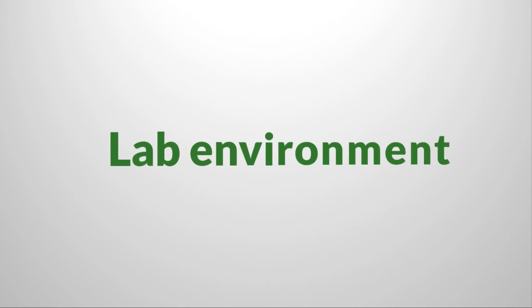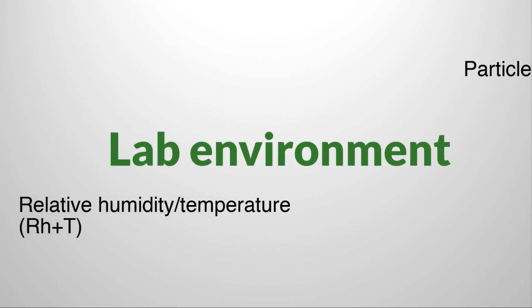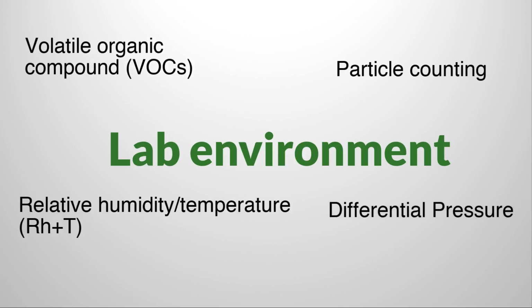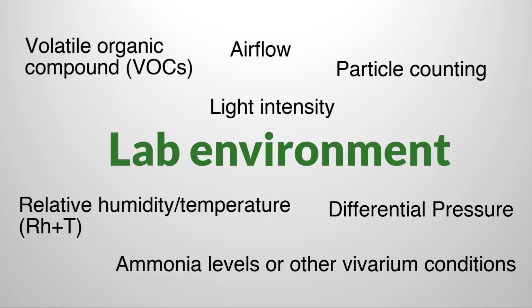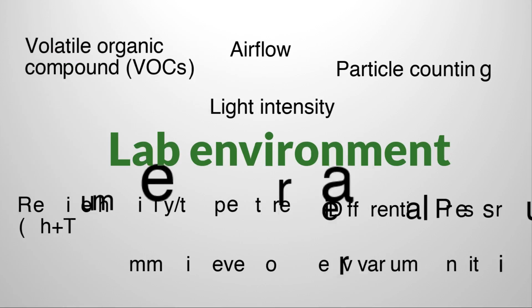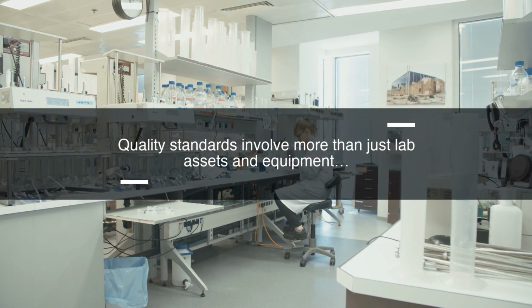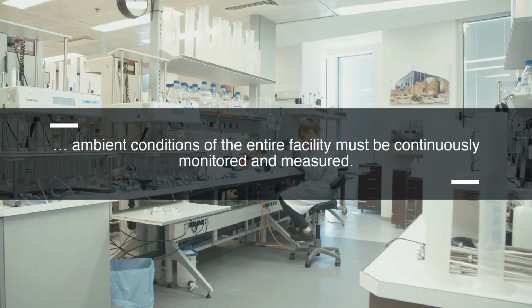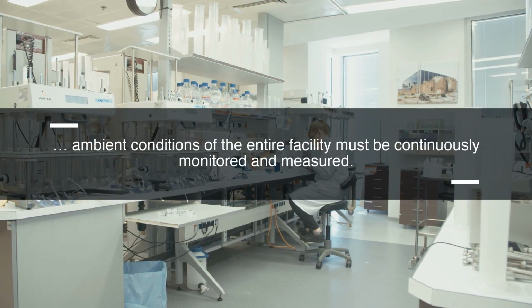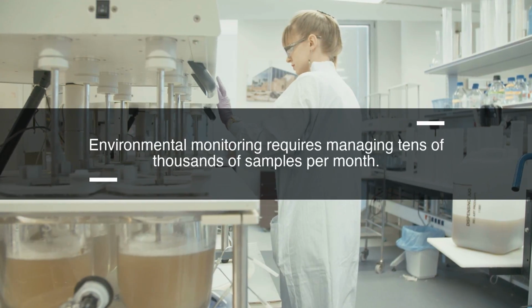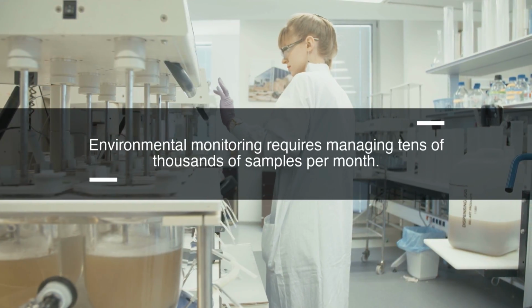Lab environment, including relative humidity, temperature, particle counting, VOCs, differential pressure, light intensity, airflow, ammonia levels, or other vivarium conditions. It isn't just laboratory assets and equipment that must adhere to GXP quality standards, but also the ambient conditions of the entire facility, from temperature and humidity to particle counts and VOCs. All of these areas must be continuously monitored and measured. Environmental monitoring requires managing complex schedules for collection and analysis for thousands, even tens of thousands, of samples per month.